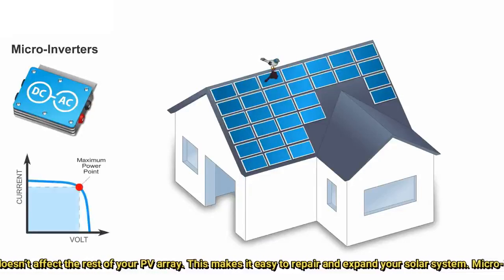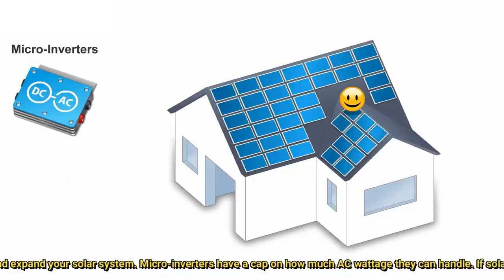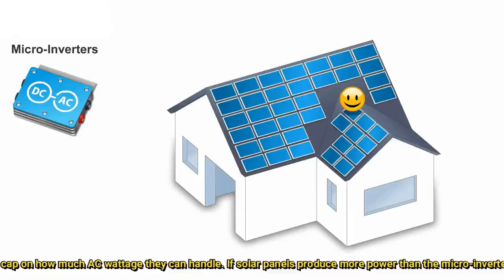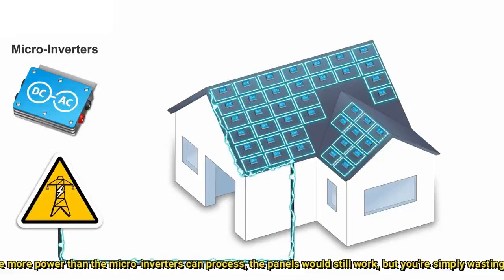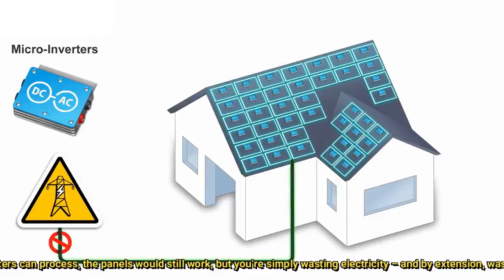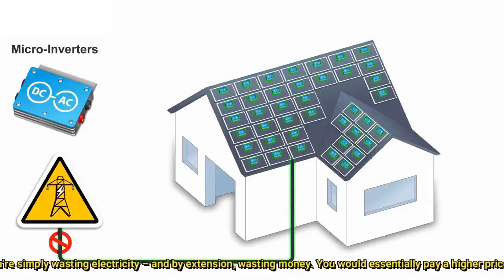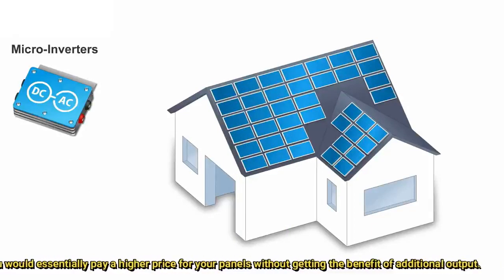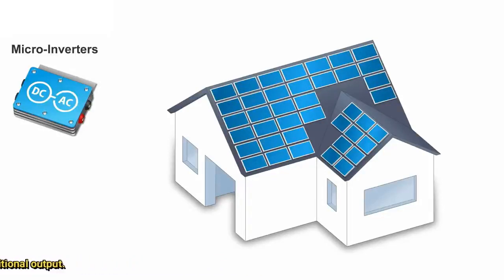This makes it easy to repair and expand your solar system. However, microinverters have a cap on how much AC wattage they can handle. If solar panels produce more power than the microinverters can process, the panels would still work, but you are simply wasting electricity and, by extension, wasting money — essentially paying a higher price for your panels without getting the benefit of additional output.